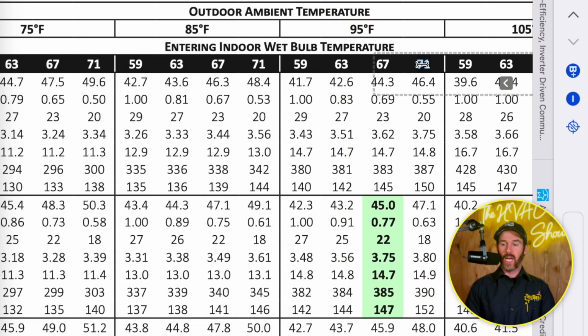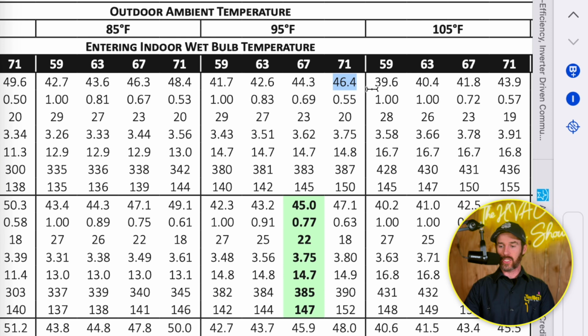And so 67 degrees, so this is not going to be like the temperature you would see on your thermostat, right? So 71 degrees wet bulb is not like what you see on your thermostat. Your thermostat is taking a dry bulb temperature reading. So when it says 71 degrees for the indoor wet bulb temperature, you can see this thing is putting out 46,000 BTUs of cooling capacity, which is almost 4 tons. There's 12,000 BTUs per ton.